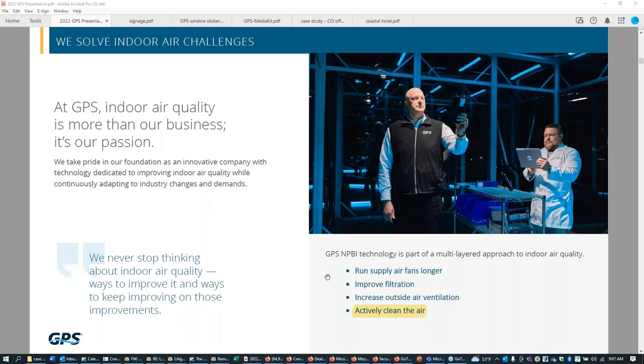Increase outside air ventilation. Some people took this to mean go to 100% outside air. Of course, most buildings don't have the capacity to do that. So the guidance really should have said, bring in as much outside air as your systems can tolerate, but don't sacrifice temperature and humidity control.